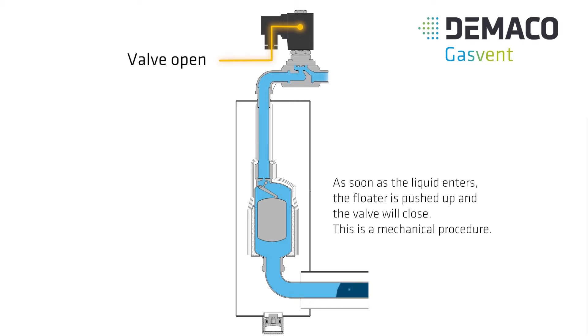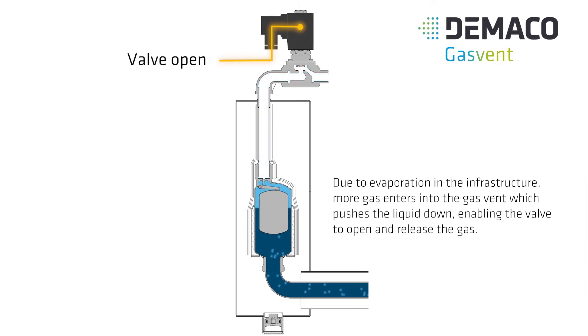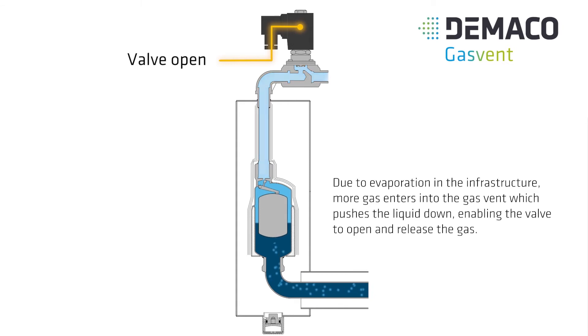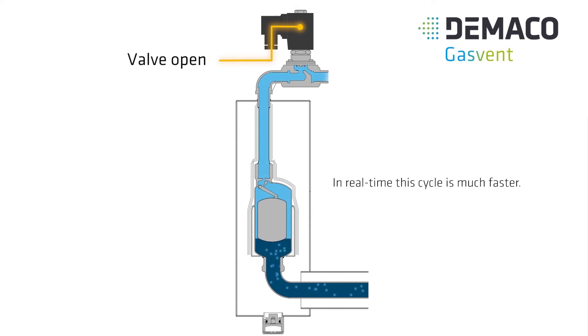As soon as the liquid enters, the floater is pushed up and the valve will close. This is a mechanical procedure. Due to evaporation in the infrastructure, more gas enters into the gas vent which pushes the liquid down, enabling the valve to open and release the gas. In real time this cycle is much faster.